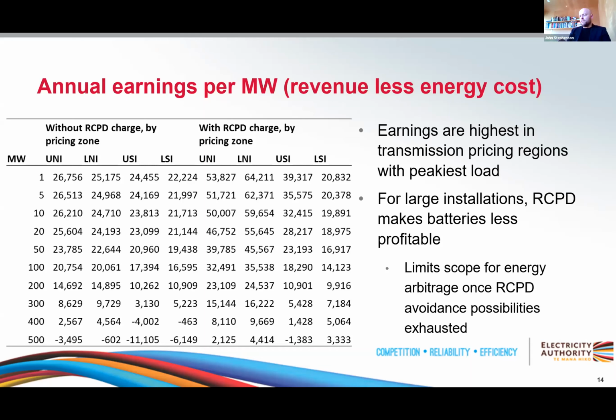One thing that fell out, a little less obvious going into the analysis, is that the presence of an RCPD charge, while it incentivizes installing batteries to avoid charges to one degree or another, can actually constrain battery investment for price arbitrage or energy arbitrage reasons. This is because peak periods are not always when wholesale energy prices are highest, so there's an opportunity to arbitrage by charging a battery during one period and discharging at the peak or a nearby shoulder, which makes the battery operation profitable. But if you step into peak periods while charging, you increase your exposure to those RCPD charges.